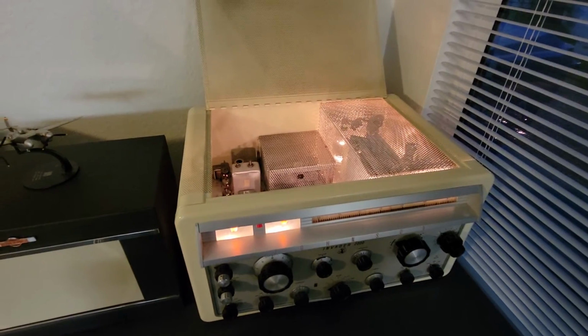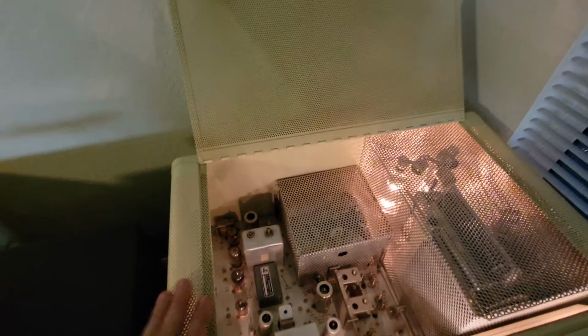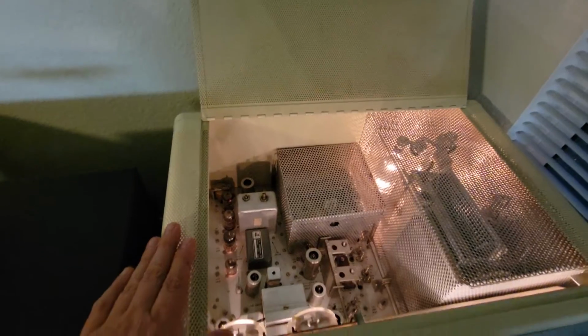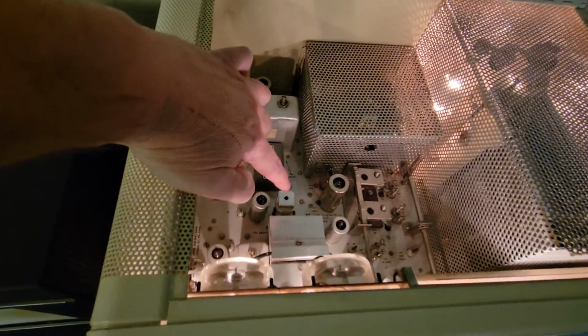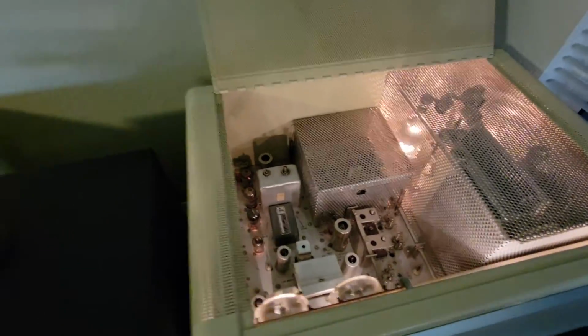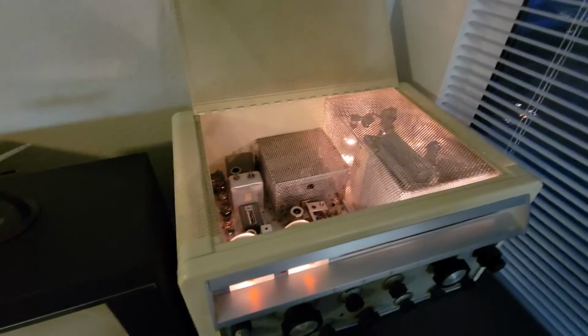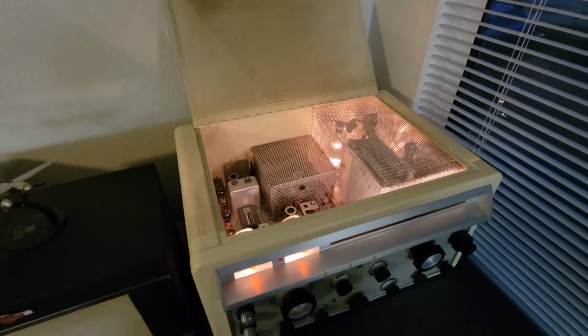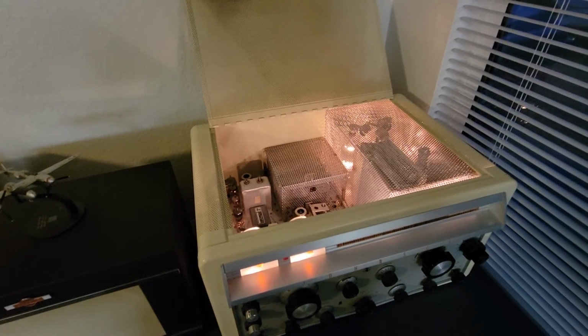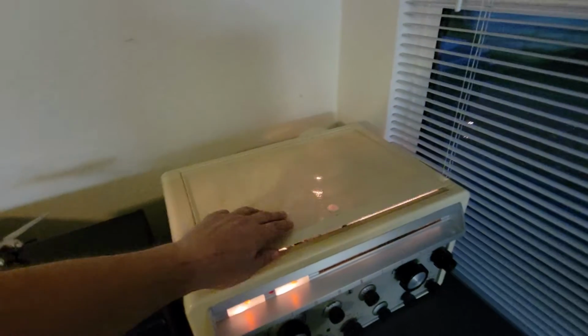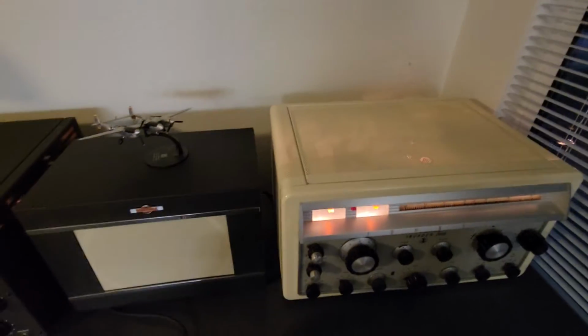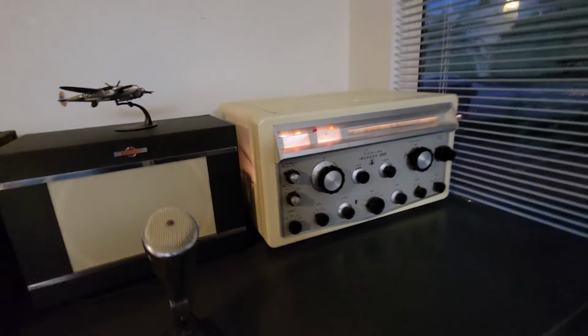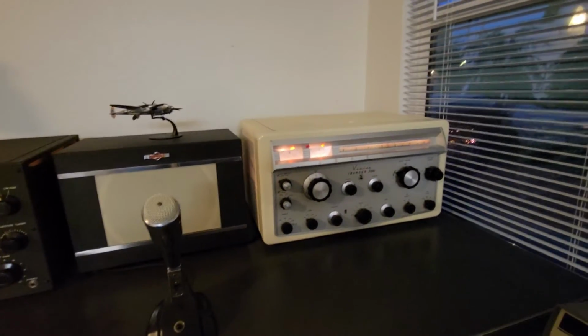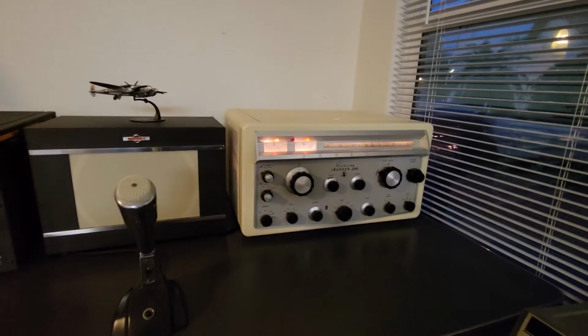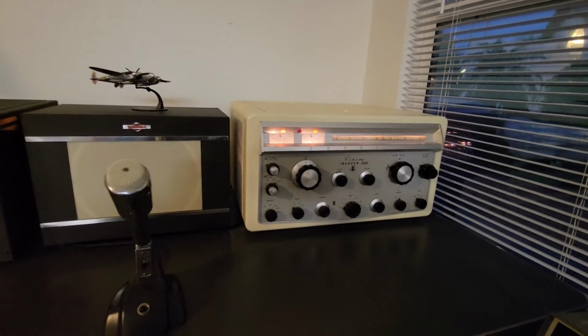Alignment - one of the biggest problems with the 200 and the 2000 is this transformer right here, this little IF transformer. That's the driver transformer, and those are always bad. That's why these things act the way they do. There's mica capacitors built into the bottom of the transformer, and those capacitors go bad, so you can't obtain a peak in drive.